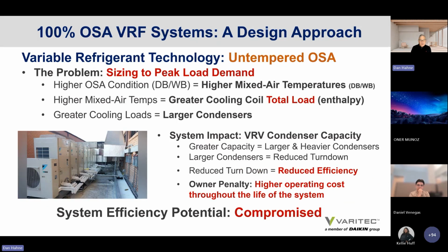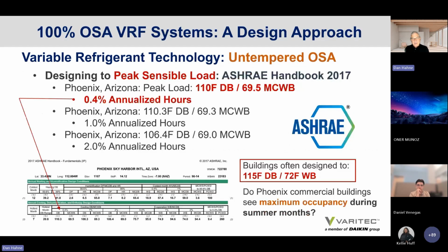The problem is that we're at peak summer design load for very few hours out of the year. So these systems are designed to meet that, but the rest of the year, they're not operating at the promise of their full efficiency levels. So sizing to peak demand loads results in higher mixed air temperatures at fan coils, greater cooling coil total loads, larger condensers, reduced turndown capability at the condensers because of their being oversized. Certainly when a building is in part load conditions such as fall, winter, or spring, the owner pays a higher operating cost and system efficiency is compromised. And these systems have to include design strategies in conformance to standard 15 that will handle the pounds of refrigerant necessary to serve these systems.